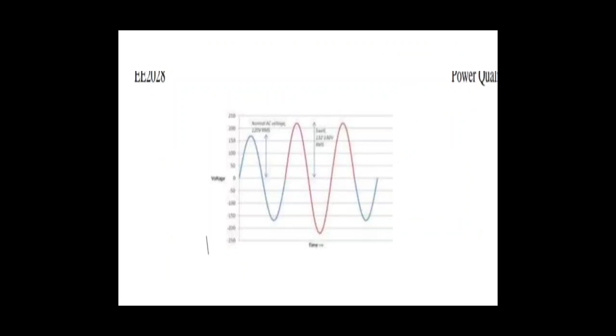Voltage unbalance, as I said, is any difference in the voltage magnitude from the other phase values. In a balanced system each phase has similar magnitude voltage and current, and they differ from each other by 120 degrees. If there is any difference in their magnitudes or in their phase angle, then that condition is an unbalanced supply system. Here we give the definition. In a balanced system, the three line to neutral voltages are equal in magnitude and phase differences from each other by 120 degrees.